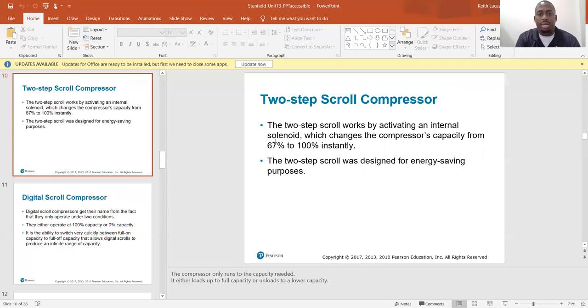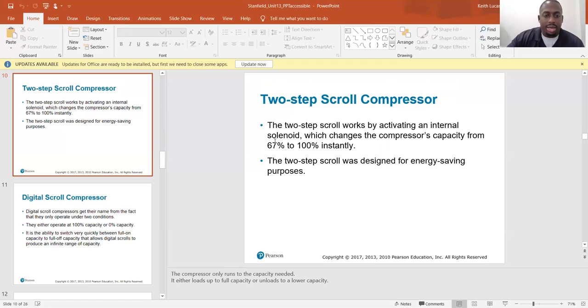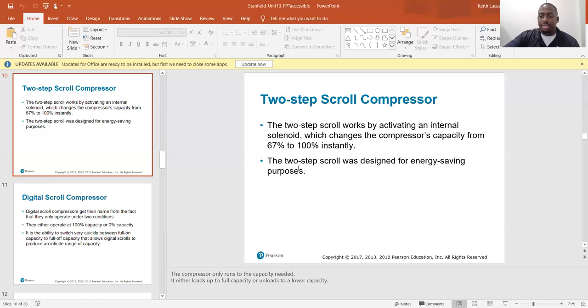Two-step scroll compressors work by activating an internal solenoid that changes the compressor's capacity from 67 percent to 100 percent instantly. They were designed for energy-saving purposes — the compressor only runs to the capacity needed, either loading to full capacity or unloading to lower capacity based on the system load.